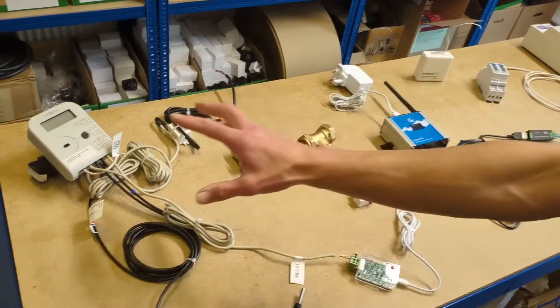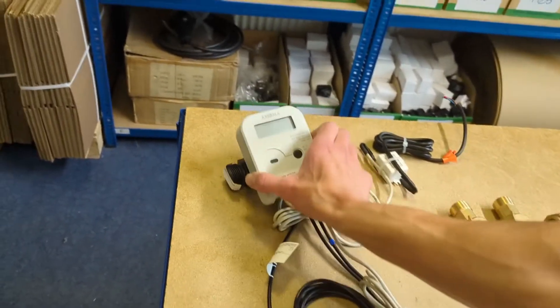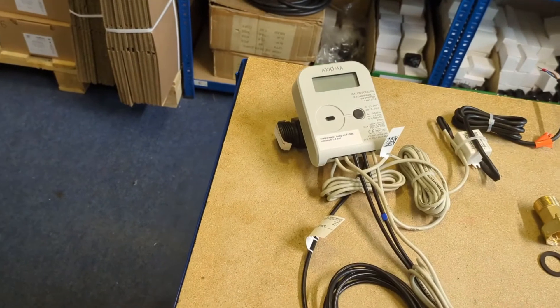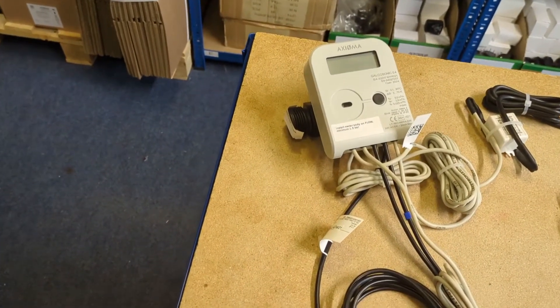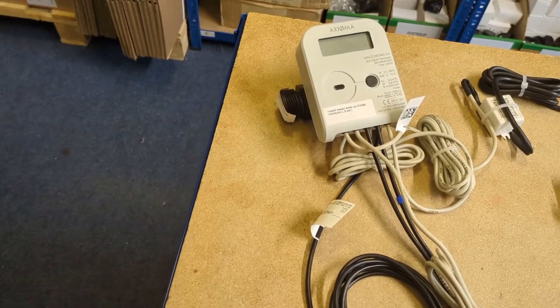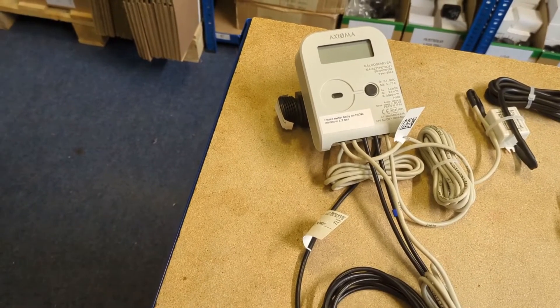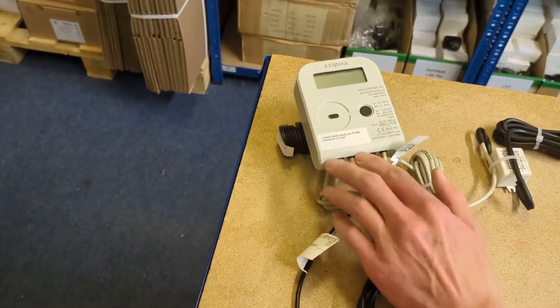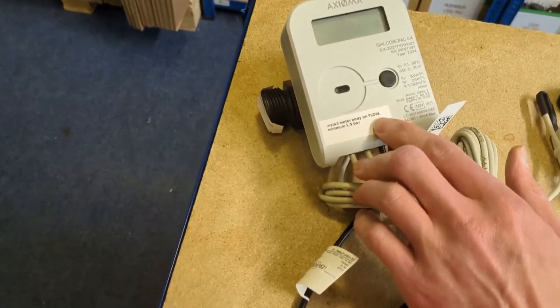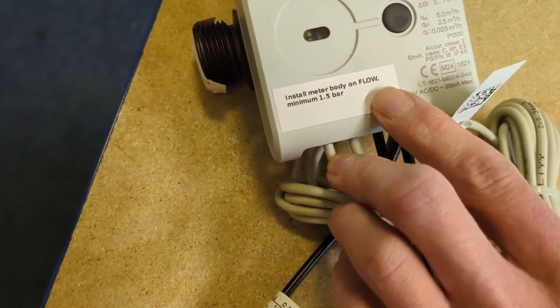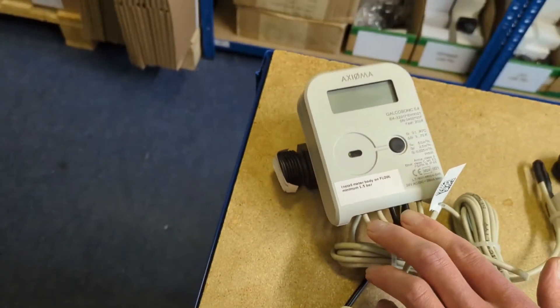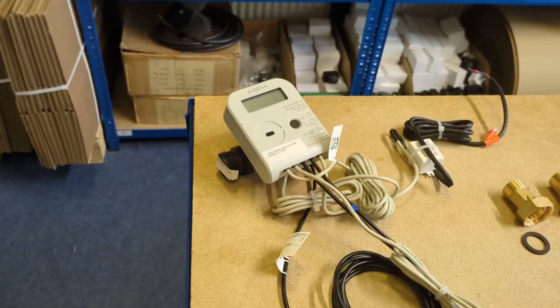We'll start with the heat meter. This measures the heat output from the system and needs to be installed on the primary pipework. Generally the heat meter body needs to be installed on the flow, but there'll always be a sticker on it to confirm that. Double check with the sticker where the heat meter needs to go.